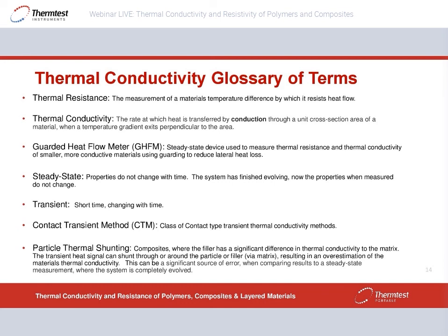For samples like bricks, can we test conductivity? Of course. The plates should come together on the sample in an intimate manner. There's a contact agent to fill in any imperfections, but certainly bricks and concrete are great samples for this particular method.